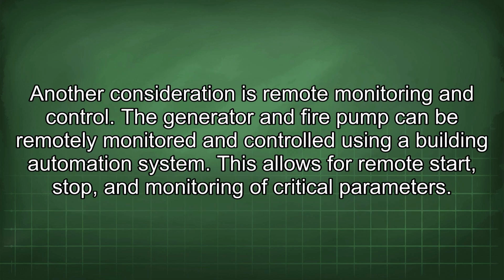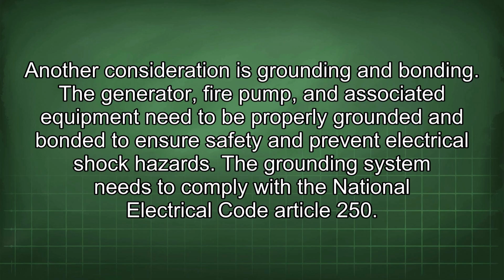Another consideration is remote monitoring and control. The generator and fire pump can be remotely monitored and controlled using a building automation system. This allows for remote start, stop, and monitoring of critical parameters. Another consideration is grounding and bonding. The generator, fire pump, and associated equipment need to be properly grounded and bonded to ensure safety and prevent electrical shock hazards. The grounding system needs to comply with the National Electrical Code Article 250.